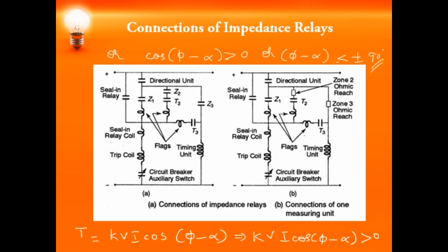This directional relay uses 2 pairs of contacts. One pair will be placed in series with the impedance relay, and the other pair will be connected to energize the auxiliary relay. The contacts of the auxiliary relay, when it is de-energized, short circuit the current coil of the impedance relay. The contacts of the auxiliary relay will be opened when the fault occurs in the forward direction.